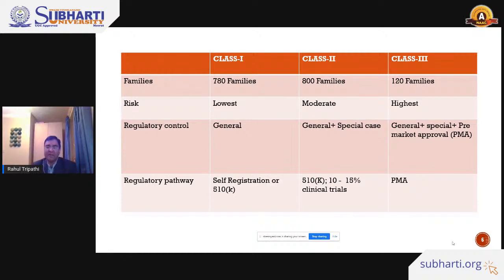For regulatory control, class 1 is very lightly regulated. You just need to go to the FDA website and do the self-registration, and if the medical device is considered very low risk, you can register your product in the class 1 category. The regulatory pathway is either self-registration, or you can fill in the form according to the FDA, 510(k). That's the regulatory pathway for class 1. Class 2 is considered moderate risk medical devices. There is regulatory control, general plus specific, basically.